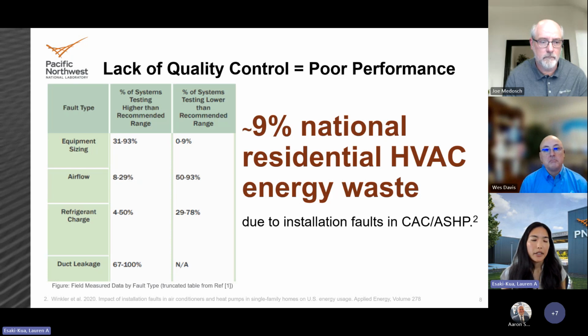This table is from that previously mentioned EERE study, mentioning the primary fault types found in residential buildings: improper equipment sizing, improper airflow, improper refrigerant charge, and duct leakage, which are leading a lot of these systems to test outside of the recommended range for optimal system performance.